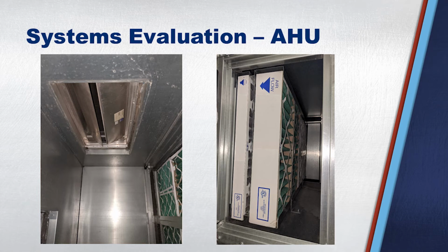Looking at the unit, we looked at the filters. 2 issues. And this is actually in the direction of airflow, left to right. This filter is a little tougher to see, but it's crushed in, and you're not really going to get the right airflow through it, so you're impacting it. And the fact that the filters are in backwards is not a huge deal. We confirmed with them that they weren't just turning them around, so that was okay.